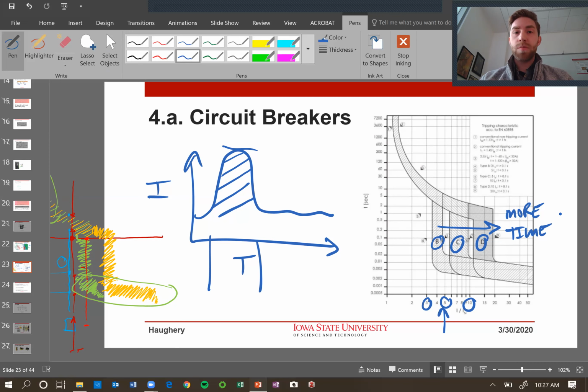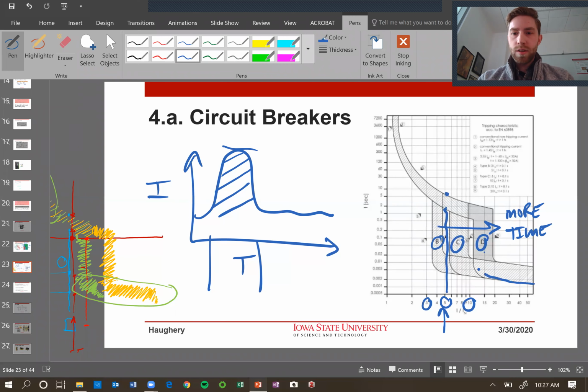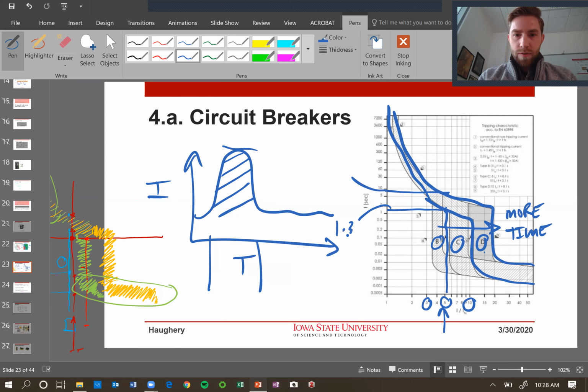So if I have a 100 amp circuit breaker, but it's 5 times, so it's 500%, 500 amps, how long will that take to trip a class D circuit breaker? It will take anywhere from here to here on my class D circuit breaker. So here's my class D, and it will be anywhere from here to here. So that's 1.5 seconds, all the way to, it looks like, 7.5 seconds. So of course there's a dead band, there's a range there.